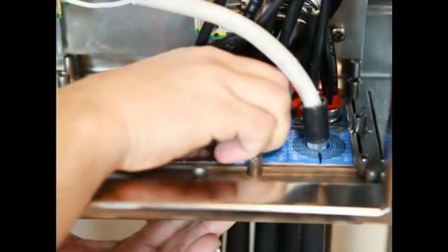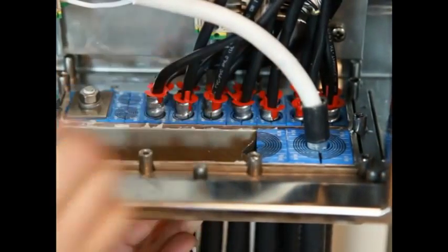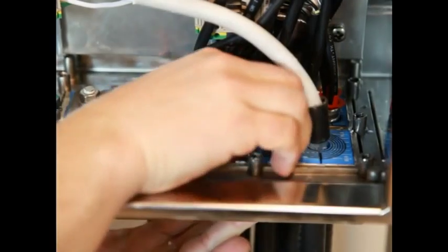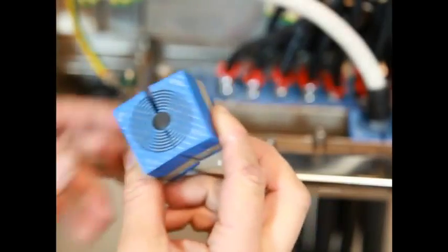Prepare the new cable according to the instructions for metal clad or SWA cable. If required, fit an anti-short bushing at the end of the armor.